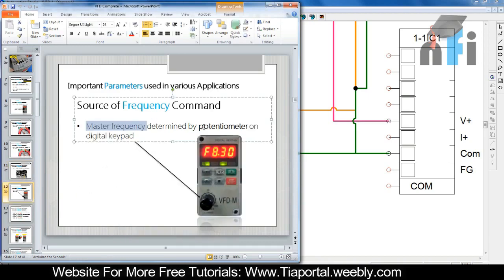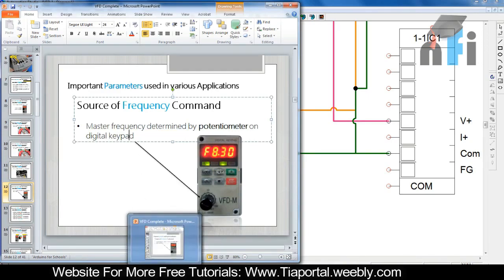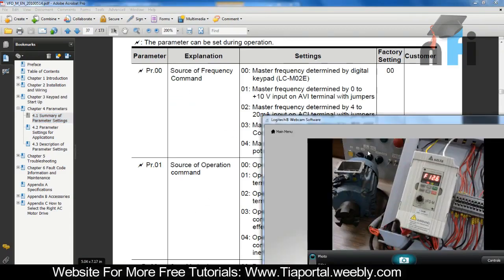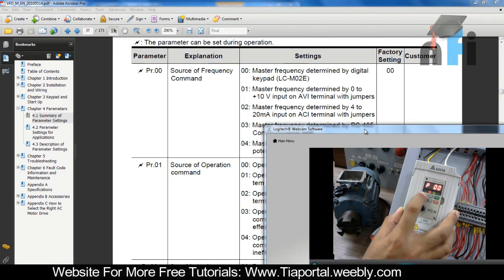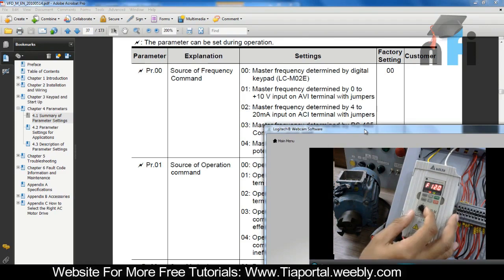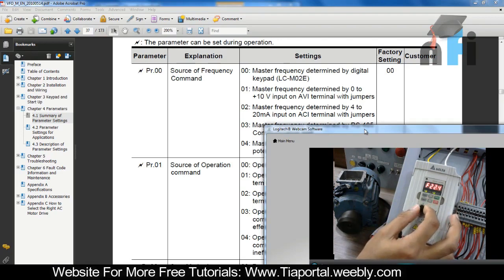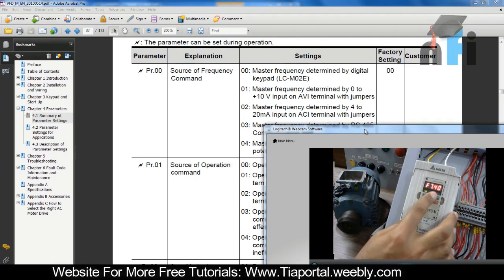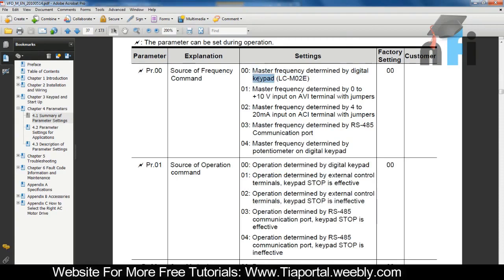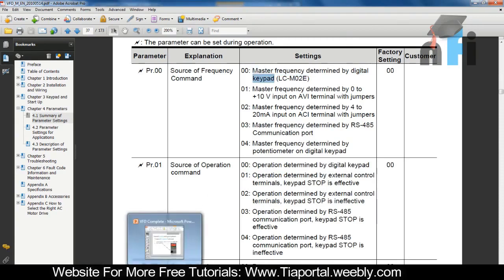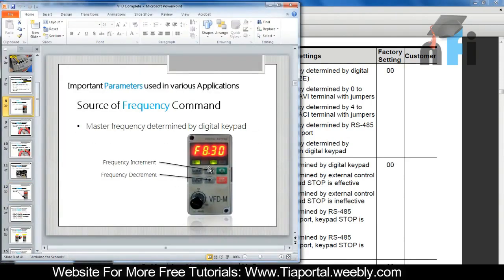The last parameter option says master frequency determined by potentiometer on digital keypad. For that, we change parameter 00 to 04. I'm going to MODE, this is 00, press ENTER, put 4, press ENTER again. Now when I go back, this frequency can be changed by this potentiometer - frequency can be increased and decreased. Now it's not taking frequency from the card, not from the buttons, but just from this potentiometer.